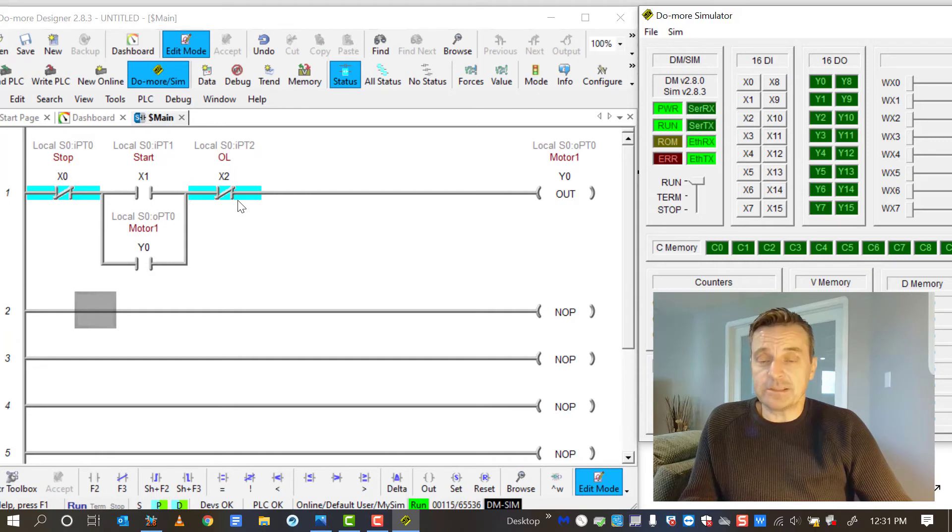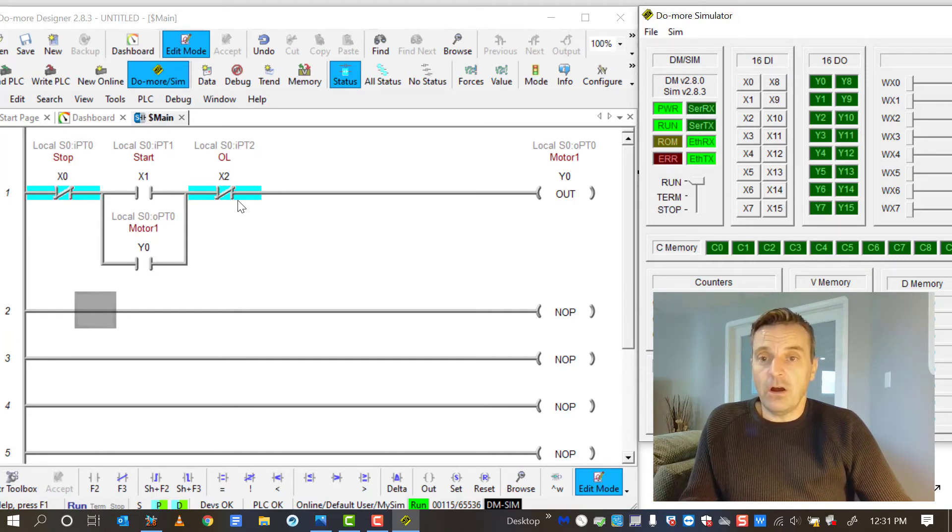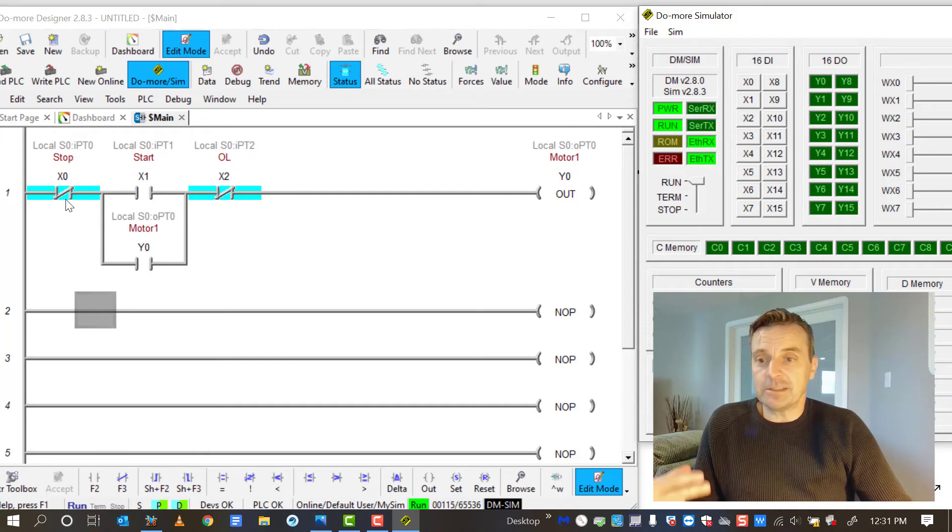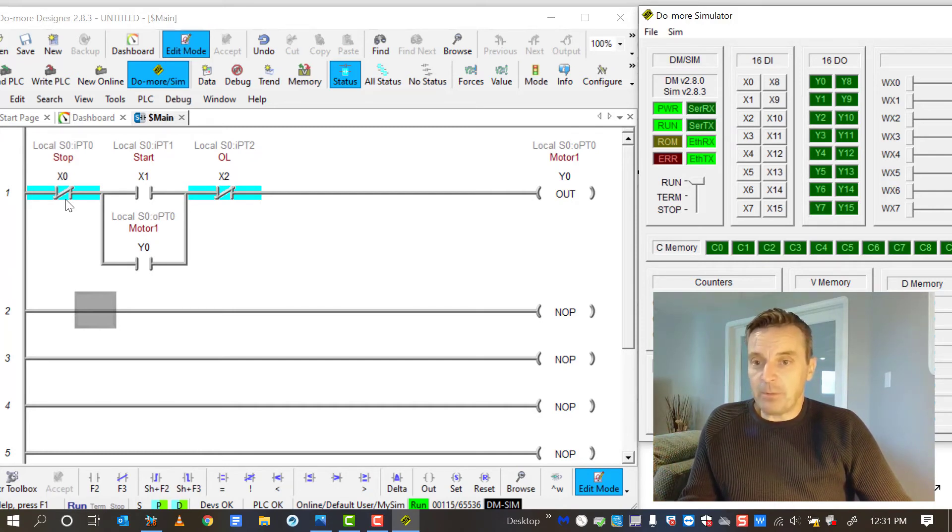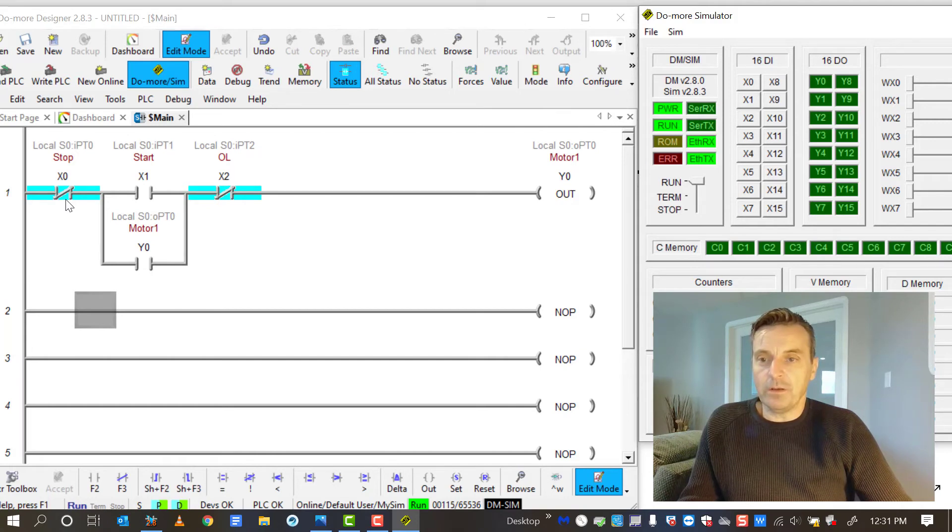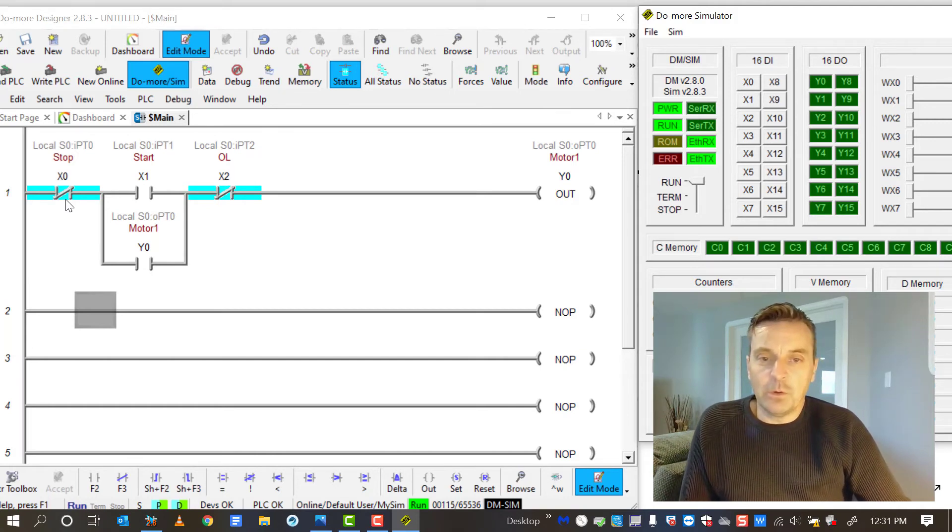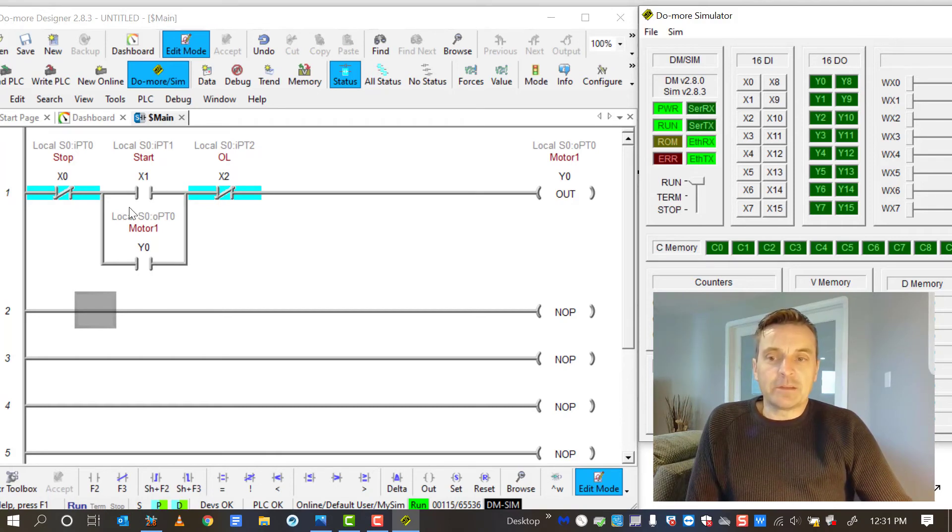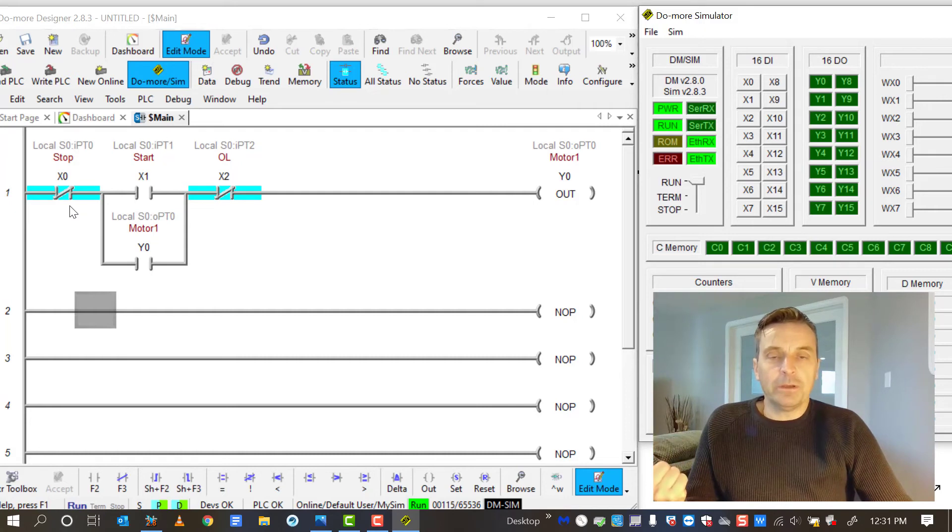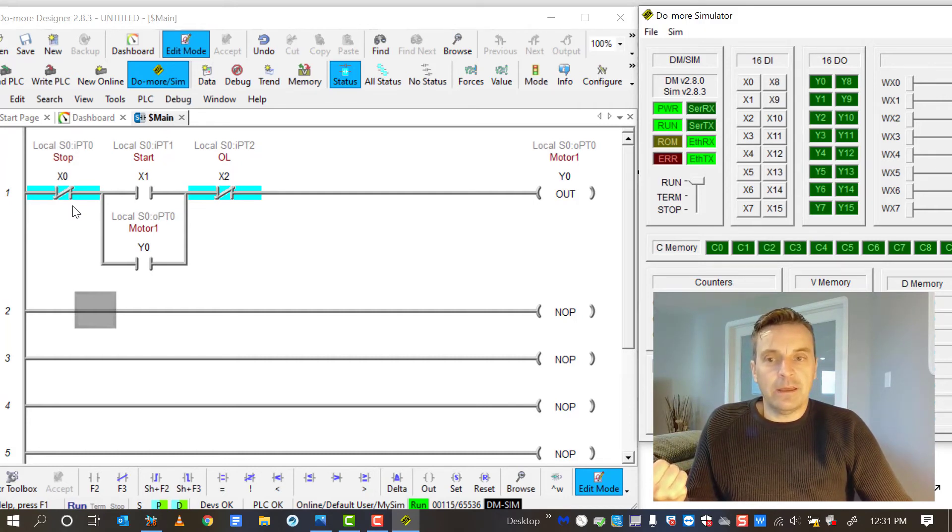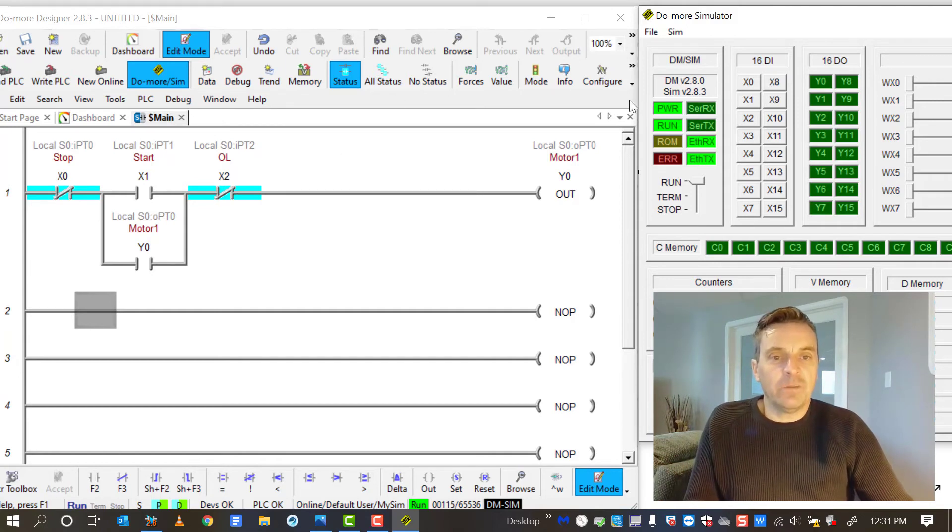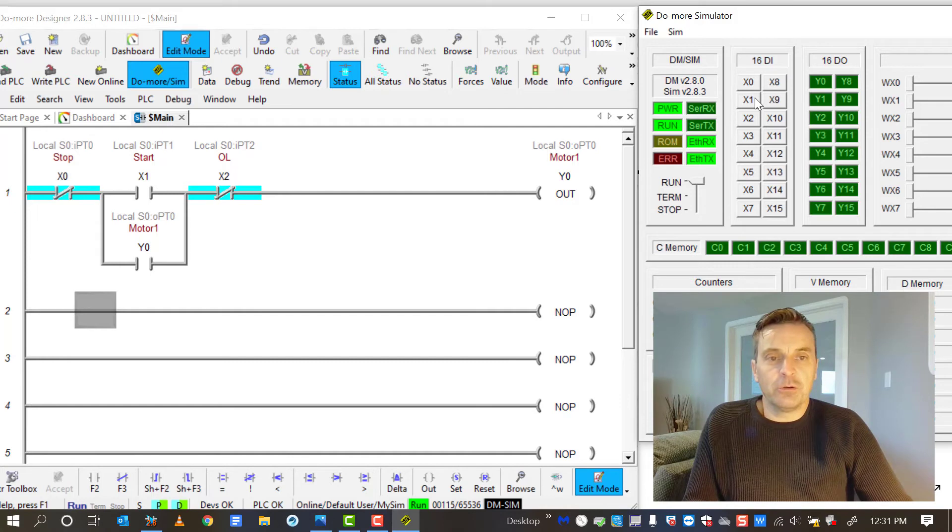To be satisfied, it actually wants to see a zero or an open state on the field device that it's wired to. Same thing over here. It wants to see an open on that stop push button, which doesn't make sense because it shouldn't be open. Having it normally closed makes it fail safe. So the only way to get this to operate would be to have a normally open stop button and a normally open overload contact. And that's just not how we conventionally do things in the electrical field.